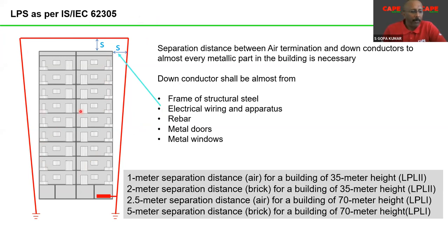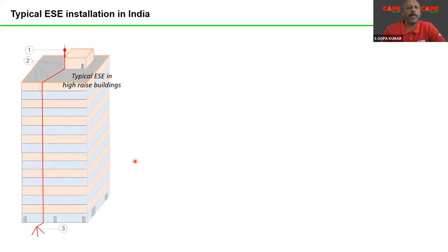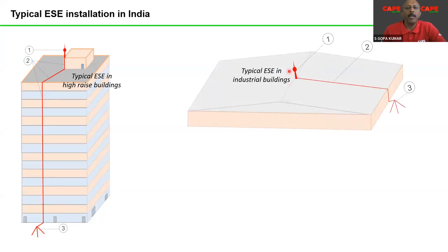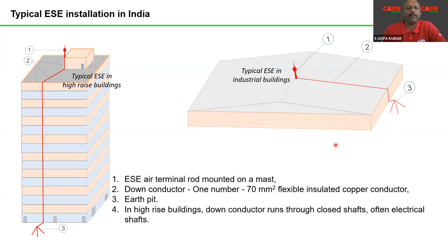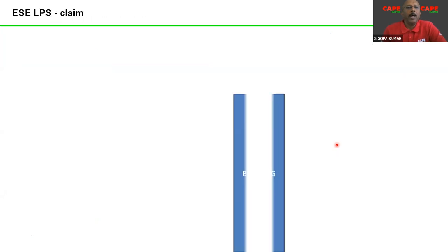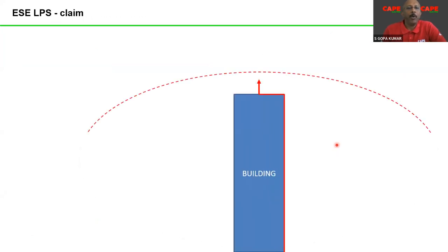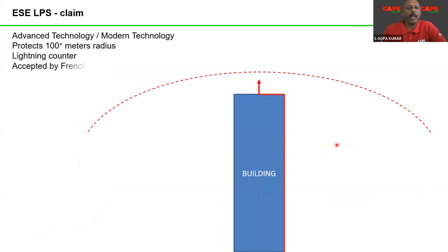The second claim: a lot of high-rise buildings in India are using a non-standard air termination called the early streamer emission system. All of you know very well, one rod, one down conductor, and one earth electrode. In a large industrial building, again, one rod, one down conductor, and one earth electrode. What is this down conductor? In 90% of cases, it is a 70 square millimeter insulated copper wire. What is the claim? These manufacturers claim that one rod protects 100 meters. And finally, the claim is that it is as per the French standard, NFC 17102.